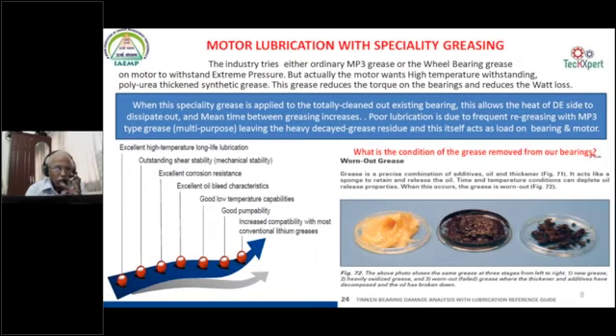Compared to conventional lithium greases or multi-purpose greases, these polyurea thickened synthetic greases which have come now are definitely reducing the torque on the bearings, driven and non-driven, especially on the driven side, and it is also energy saving. Let us look into the aspect of energy saving and safety. You are putting in labor 4 times a year to pump and re-grease, and you are not removing the old grease. We can see on the right side bottom of the chart the grease you put in at the grease gun point, what is there at the drain point, and what has come out. You can see the greasing condition, the temperature and time, and how much has gone back. The grease has to act like a sponge on the bearing and keep the rotation of the motor very smooth. Once it is not there, it is a loss to the system. That is where the localized heat shoots up to more than 100 degrees and above.